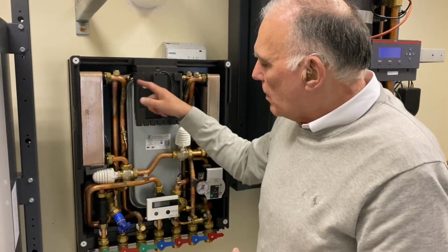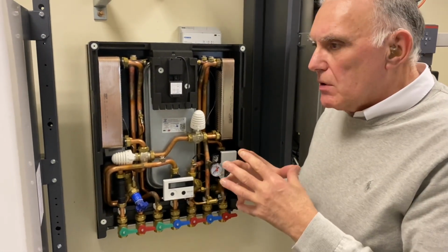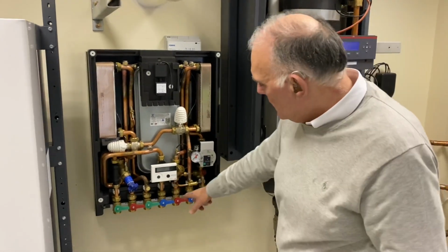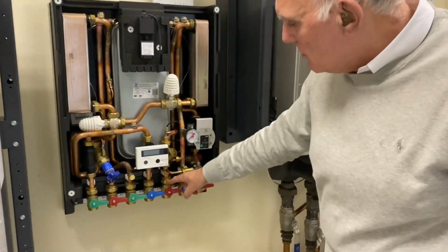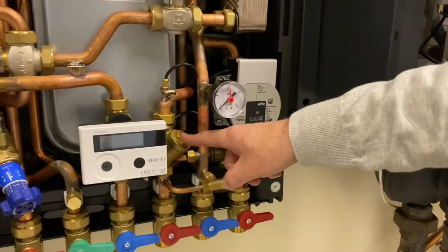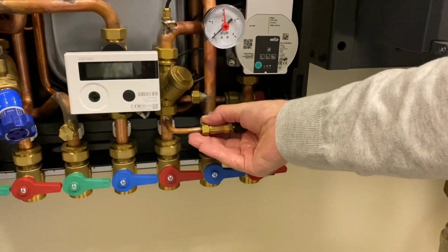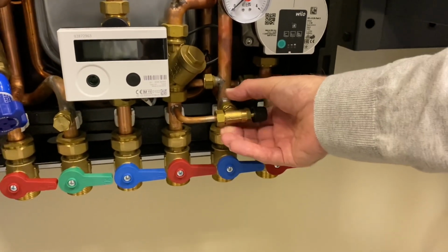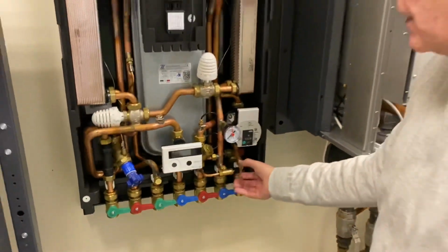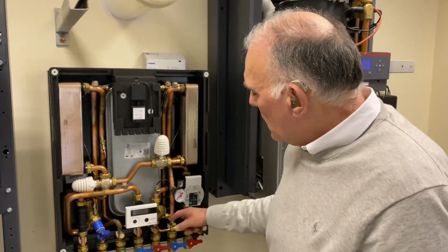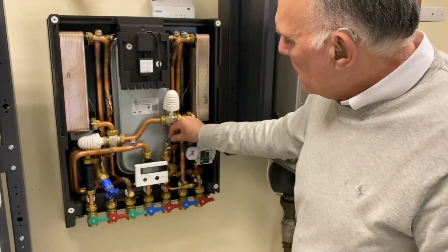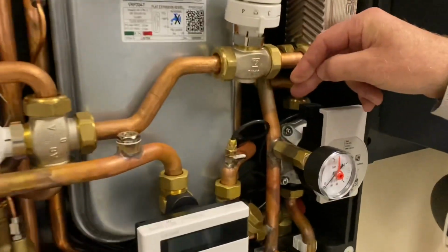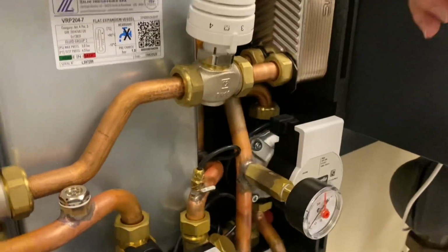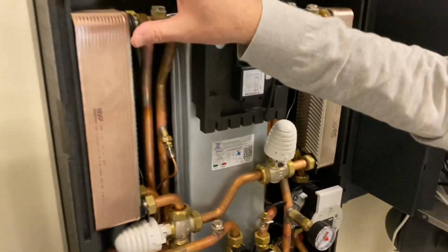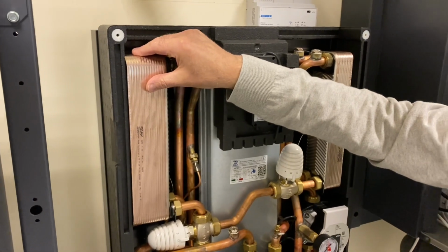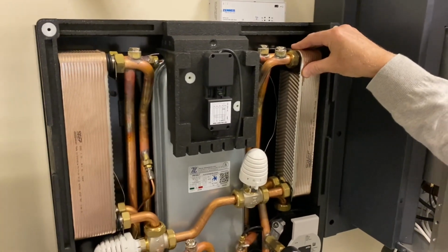So that's the cold. The primary flow, the hot pipe in from the main plant, is here. So the primary flow comes in here. There's a filter. Please ignore this filling loop because this is a continental model. We would use a standard filling loop as you're used to in the UK with a flexible hose for the UK models. But primary flow in, the temperature is sensed here. This is a sensor, and then the primary flow is split.